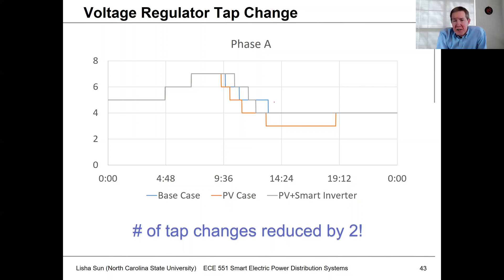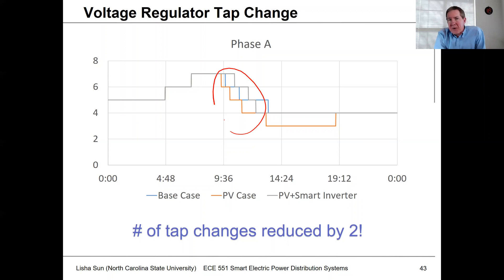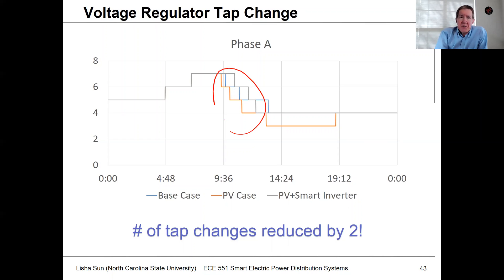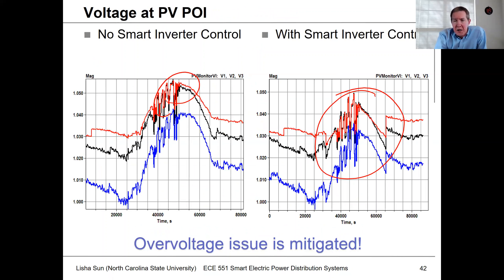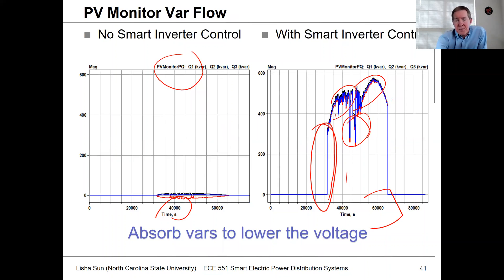Inverters are almost like variable capacitor banks. Some people have been looking at using inverters to do voltage control instead of tap changers. The problem is: would you want inverters operating all the time, even when there's no sun? And developers may not want their systems used that way. This is a research area — using inverters for var control does mean you have to oversize them a bit.